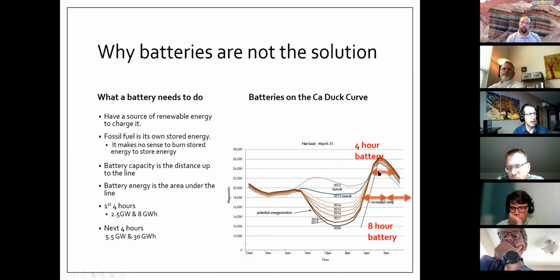I looked at that quickly and said, okay, that looks like about 2.5 gigawatts of capacity we have to have for solar to address this peak area here, and we're going to need about 8 gigawatt hours based on this being 80% of the area. But now that I look at it again, I think I overestimated that. I'd say maybe 50 or 60% of this block is actually being served by the battery, so it would actually only be like 6 gigawatt hours.